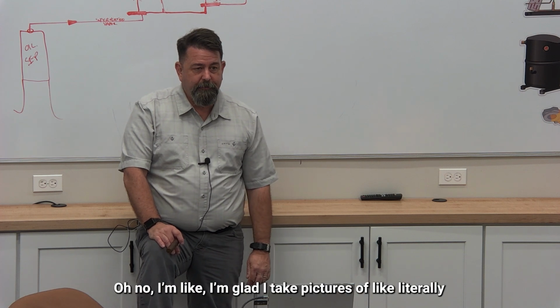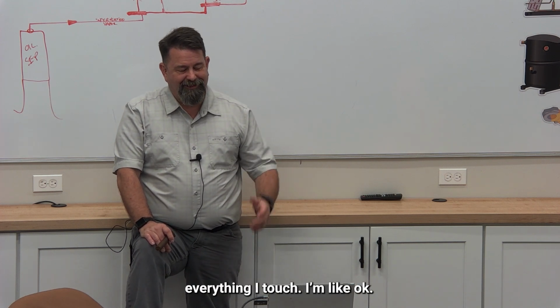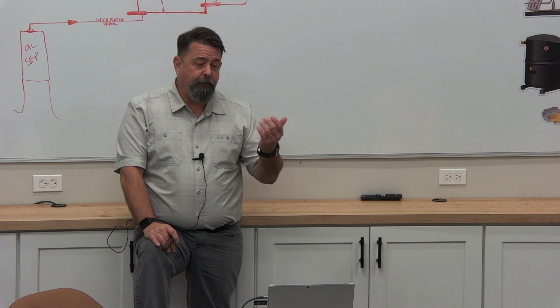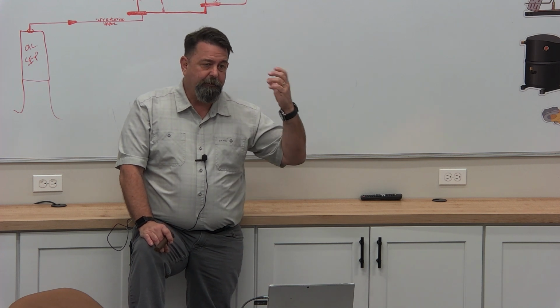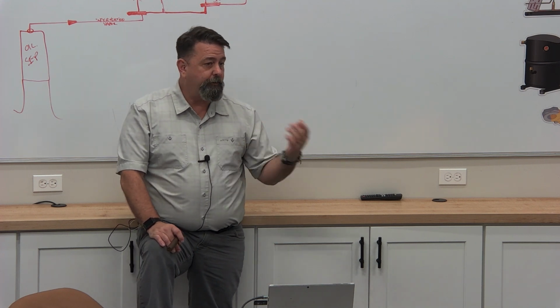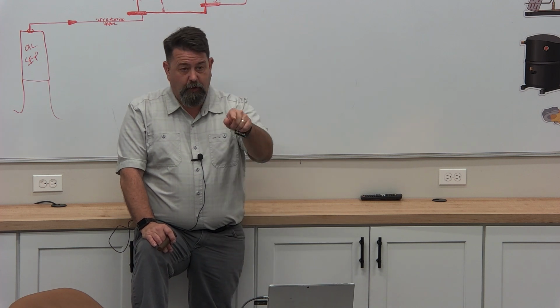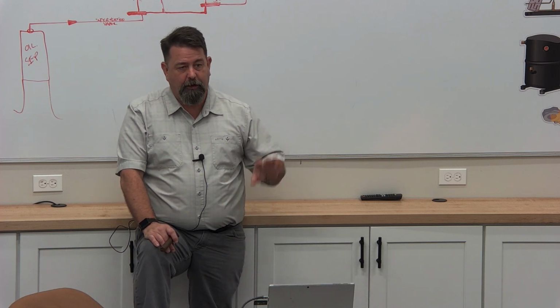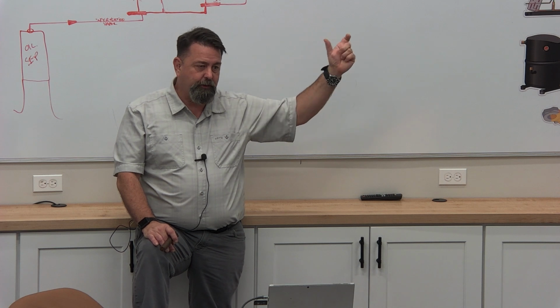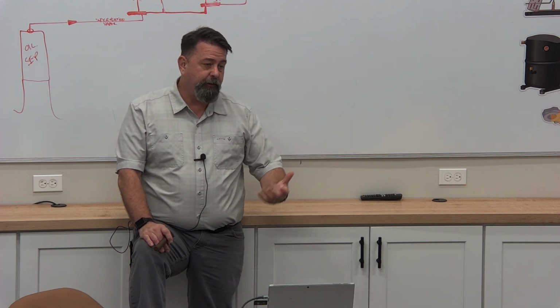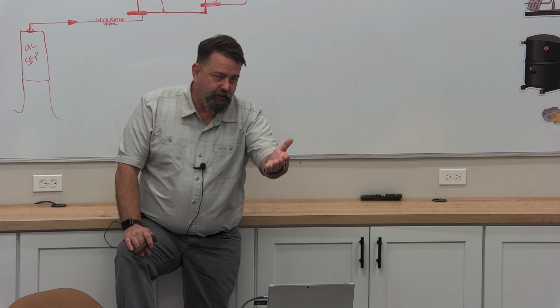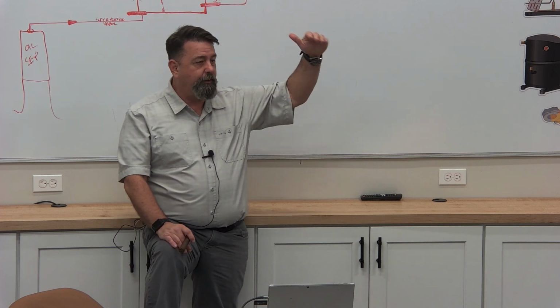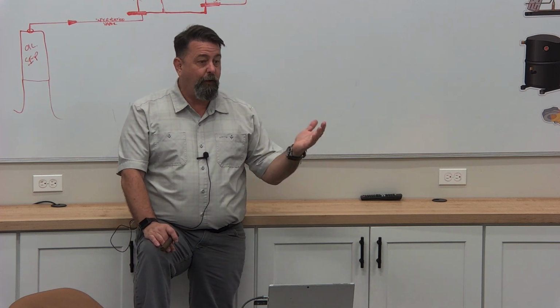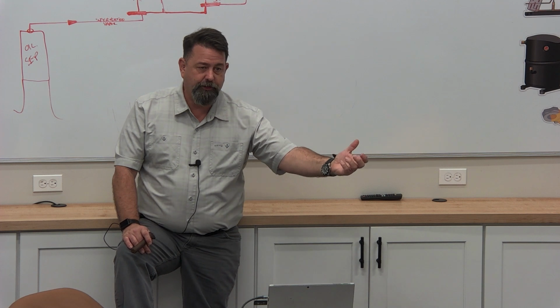I'm so glad I take pictures of literally everything. So then the VFDs went to controlling off of TD, and that's how they all are today. If you find one working, it's working off of TD. So I'm thinking that the tag you're reading there was that first attempt to actually use subcooling off the VFD. It's not really floating discharge, right? We're not changing the target of the discharge. We're just telling the VFD to ramp up and down until I have this temperature of subcooling.